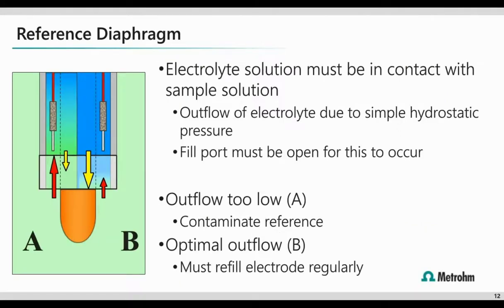So, all right, let's shift gears back to the reference electrode and take a closer look at what's happening with the diaphragm. So the diaphragm, just in general, is responsible for providing a constant outflow of the electrolyte into the sample. That means the electrolyte must go into the sample solution. We want that inner electrolyte solution to slowly drain into the sample as we're making measurements. It obviously will be draining so slow that you don't see it with the human eye, but it will be leaving the electrode. This happens due to simple hydrostatic gravity-driven pressure.